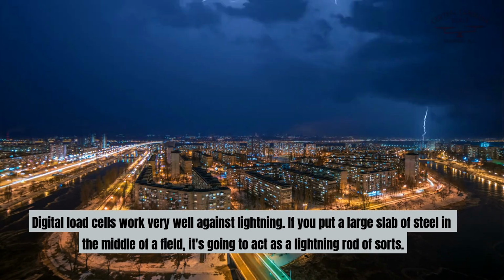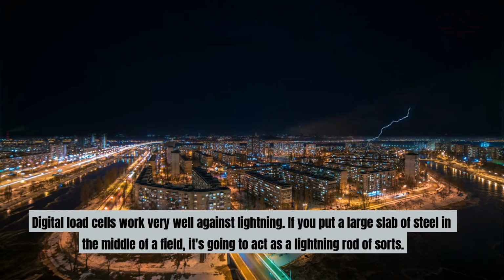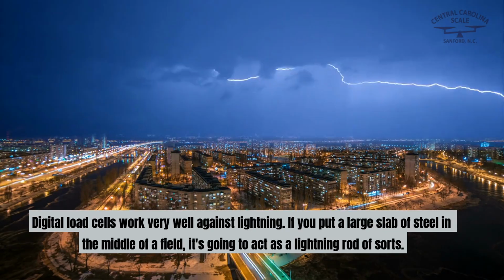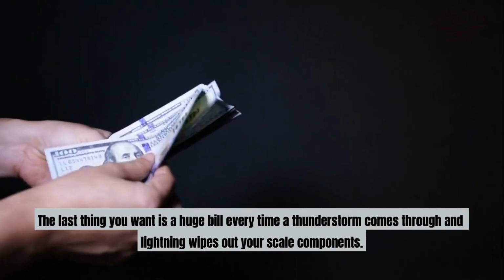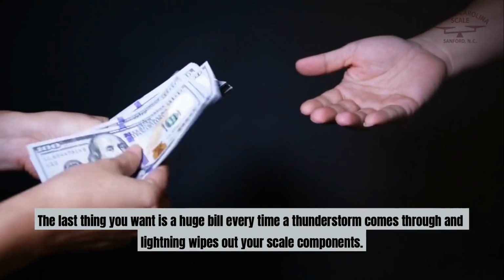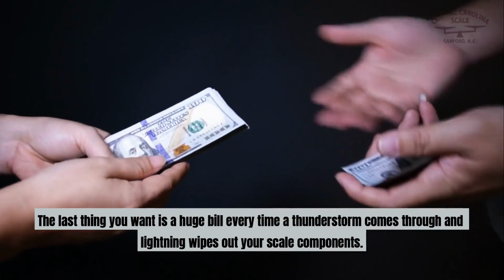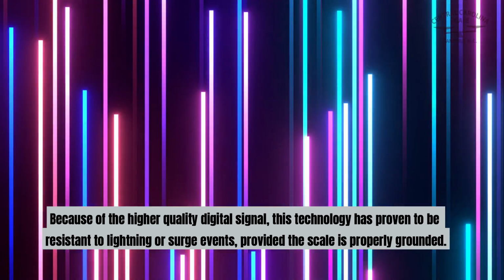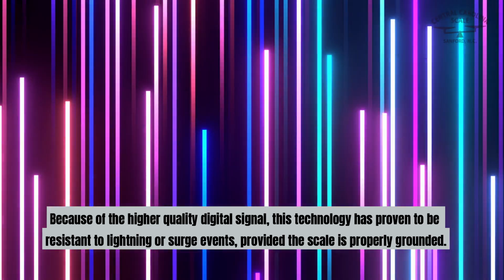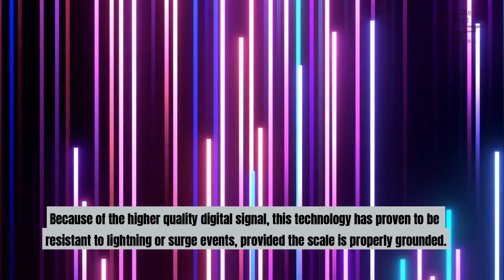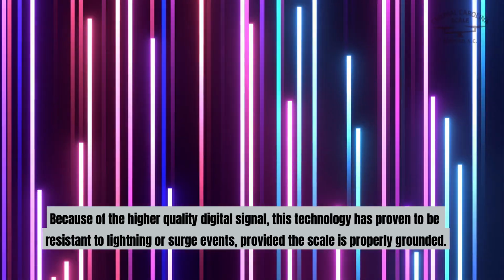If you put a large slab of steel in the middle of a field, it's going to act as a lightning rod of sorts. The last thing you want is a huge bill every time a thunderstorm comes through and lightning wipes out your scale components. Because of the higher quality digital signal, this technology has proven to be resistant to lightning or surge events, provided the scale is properly grounded.